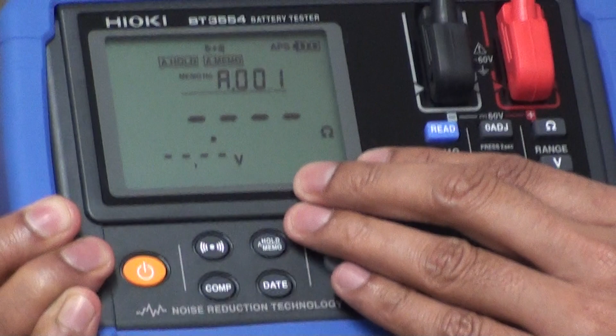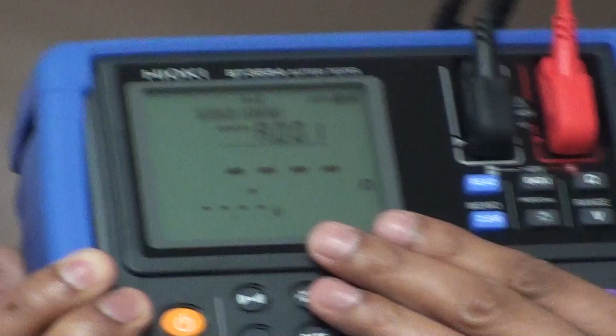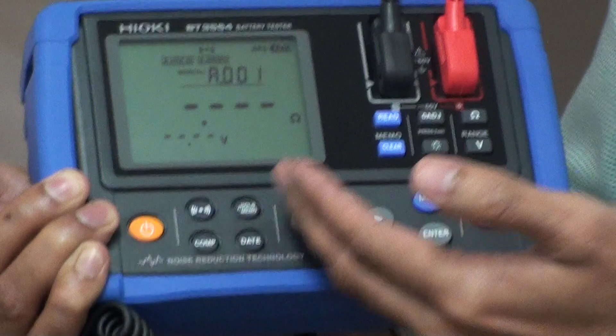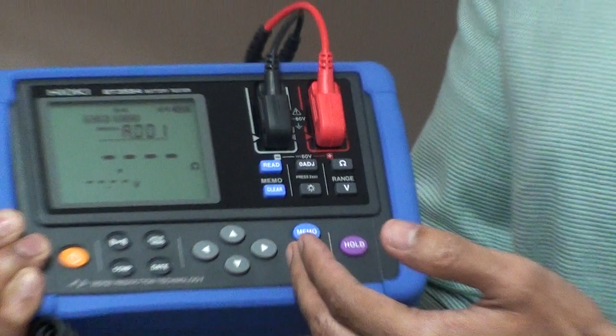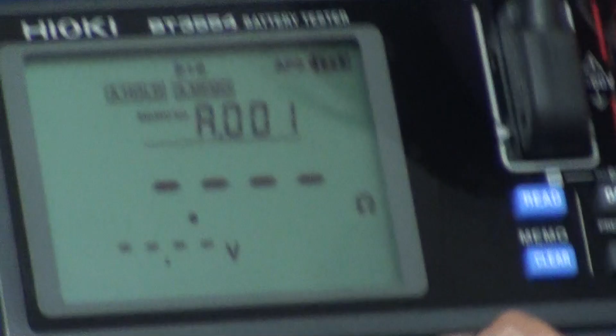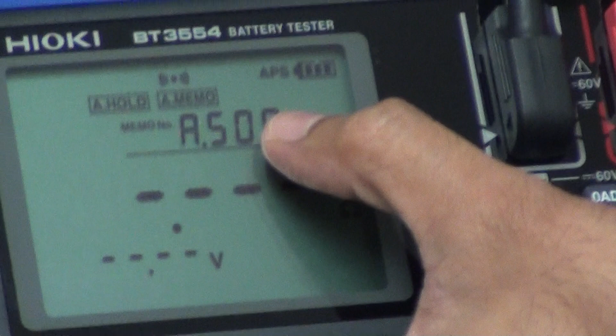Another feature in this instrument is that it will save more than 6,000 readings. Like if you have banks of more than 6,000 batteries in a single place, you can do the testing for each and every battery, and this instrument will automatically save all the data by naming 1, 2, 3 and the banks like A, B, C, D up to P. In each and every bank A to P you can save 500 readings. So you can see here on the display there is A001. Like that, if you want to move to A500, similarly you can change here A to P. So you can save up to around 8,000 data.